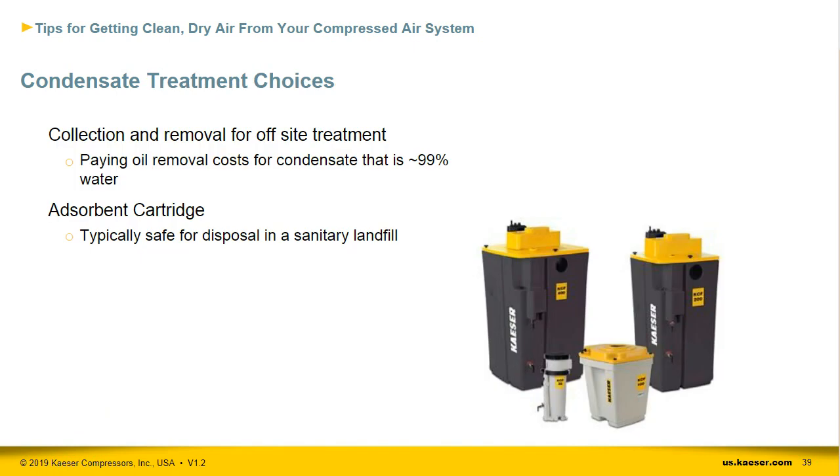There are a few common choices for condensate treatment. When choosing a disposal method, account for the costs of initial purchase, energy, maintenance, and any residual oil waste disposal when comparing your options. The simplest solution is to collect all the condensate and pay to have it removed and treated by a third party. But simple doesn't mean inexpensive. Your condensate's roughly 99% water, 1% oil, so you'd be paying a premium to have raw condensate removed from your facility by a waste hauler.